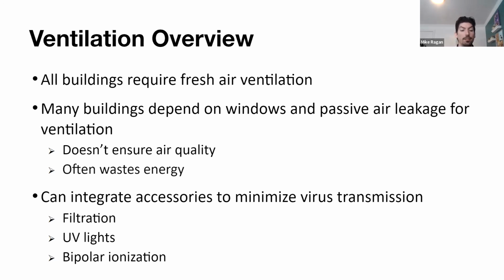But with that said, there are a number of ventilation accessories, especially in light of global events as of late, that integrate with our equipment to minimize virus transmission. Filtration: depending on the fan coil type, you can have MERV filtration up to MERV 13 in some instances. UVC lights could definitely be built into the ductwork as well in order to neutralize any mold, virus, et cetera, in the air. I will just say for those in the crowd, if anyone else like me has sat through a great number of these different types of presentations over the past 2 years, one thing I've learned about UVC light is that if you could see it with your own 2 eyes, it's not working, because that will damage your eyes. That needs to be built into the ductwork. So that's one thing I've personally learned on UVC light integration. And lastly, bipolar ionization, another high-tech method of neutralizing any contaminants in the air as well.